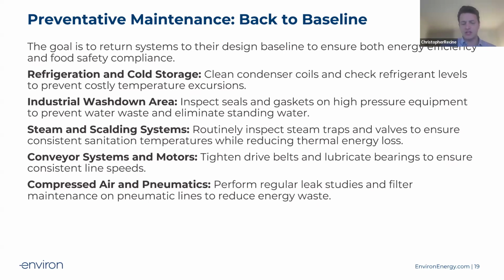The second, in terms of industrial washdown, as well as steam and scalding systems, is making sure that the gaskets, the steam traps, as well as the valves are operating properly. So doing a preventative maintenance check. Steam traps, we'd like to say at least annually. In terms of seals and gaskets, ideally more like quarterly or even more frequently. That would allow your system to not have leakage, right? Ultimately, if you have a steam system that is just passing through steam at high velocity, you are leaking a whole bunch of steam. And if it goes the other way and the valves have failed to close, you potentially have areas where you're not getting steam. And that's obviously a sanitation risk as well as an operational risk.